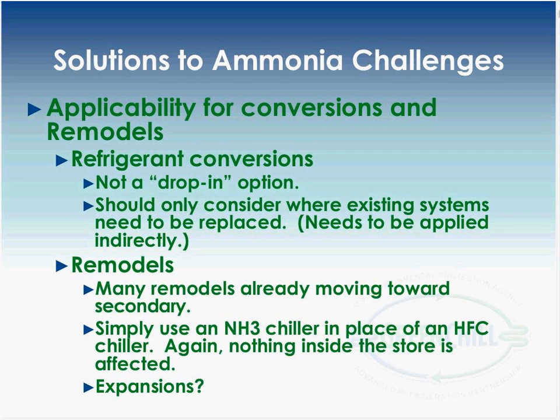I put expansions down there. Depending on what size systems commercial manufacturers start building, if you did an expansion, you could use a smaller chiller and just take over that new area. However, I don't know if that will ever be done. I think you'll get more bang for your buck by applying ammonia to the entire store and pairing it with CO2 DX on the low temp side, or a smaller CO2 secondary on the medium temp side.